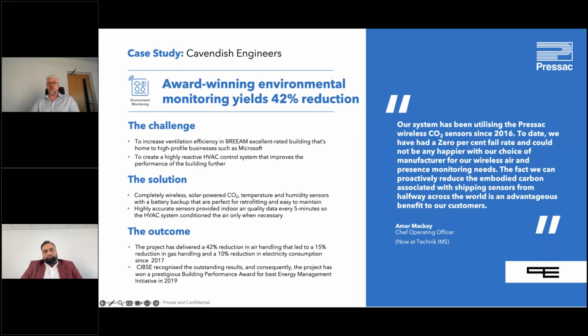The building made use of both our environmental monitoring sensors and energy monitoring, and what we realized was that the way the BMS had been set and configured to do air exchanges meant the AHUs were operating unnecessarily. By monitoring CO2 levels within the space, Cavendish engineers were able to integrate with the BMS system.